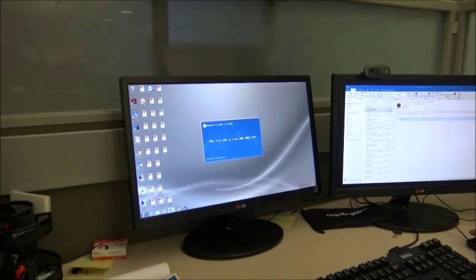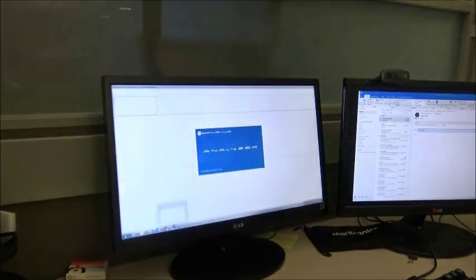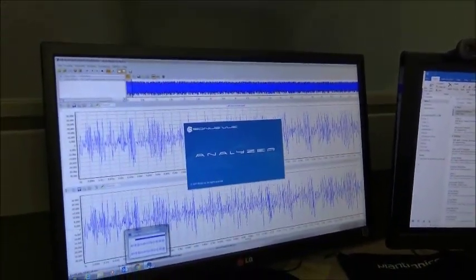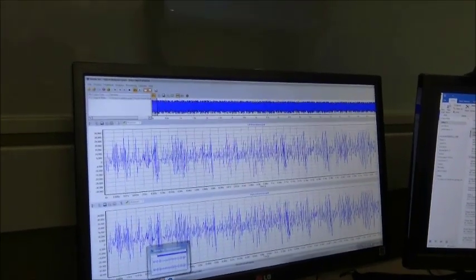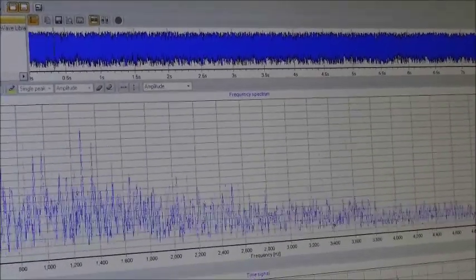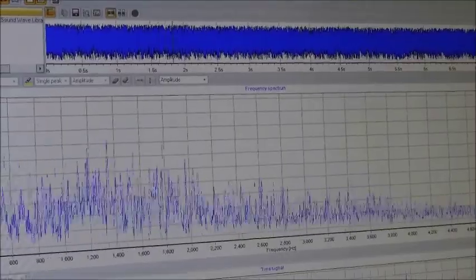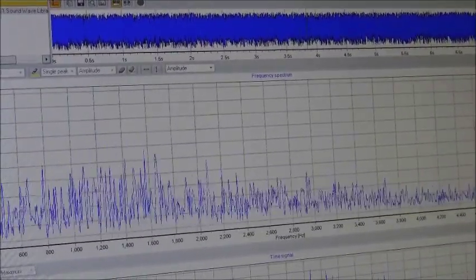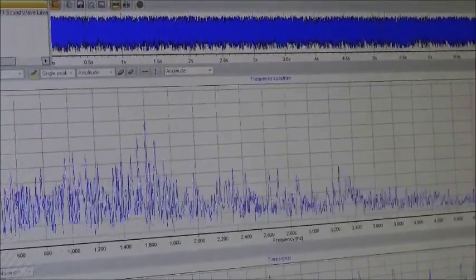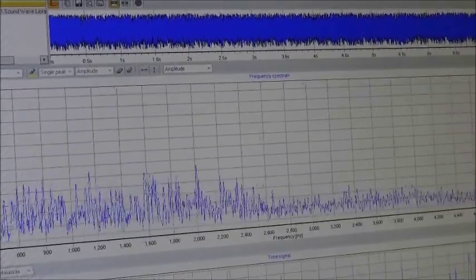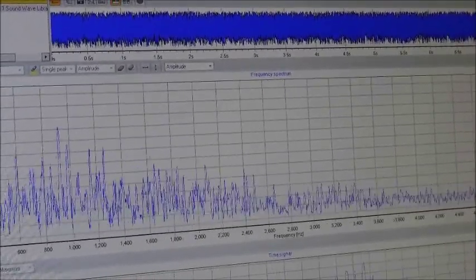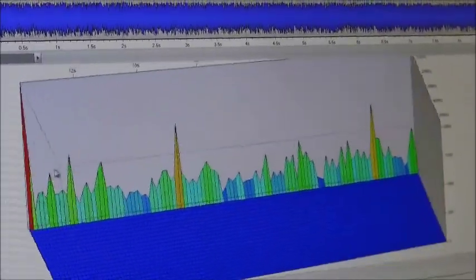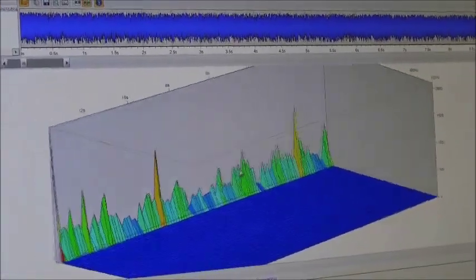Back at his desk, the technician opens the Sonus View Pro analyzer software to look at an unusual sound waveform he recorded earlier in the week using the Sonus View app and his Sonus XT handheld. He can look at the sound in the frequency domain and the time domain, or even using a 3D spectrogram. In this way, he can compare it to known examples of arcing, tracking, or corona and make a determination of what type of problem he might be seeing.